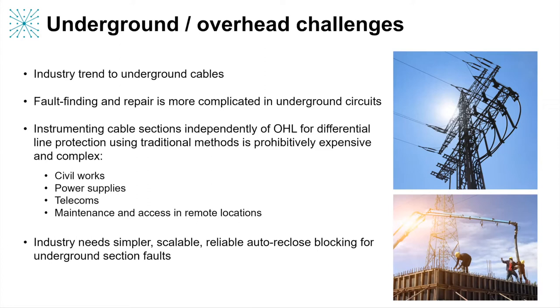Hybrid circuits are composed of both overhead and underground sections. Moving sections of the network underground means that it becomes more difficult to fault find and repair. So operators need a robust method of protection and means of protection response for these circuits. The most reliable and efficient of which would be differential protection, in which you sectionalize that hybrid circuit into discrete monitored sections — overhead and underground — and treat them separately. With that in place, the operator is informed immediately in the event of a fault whether it has occurred in the overhead or underground section.